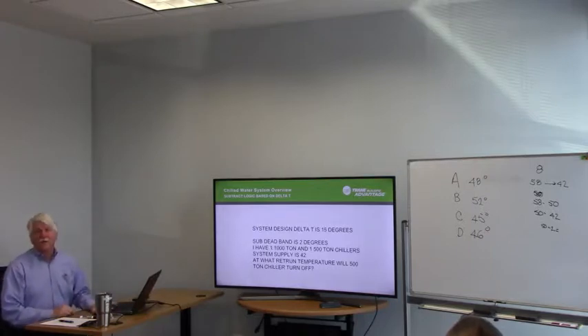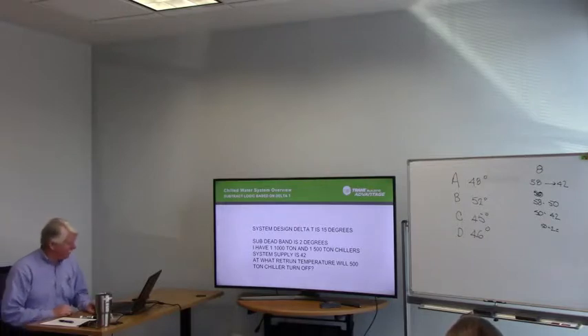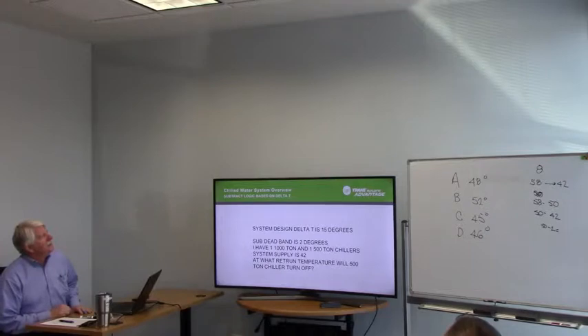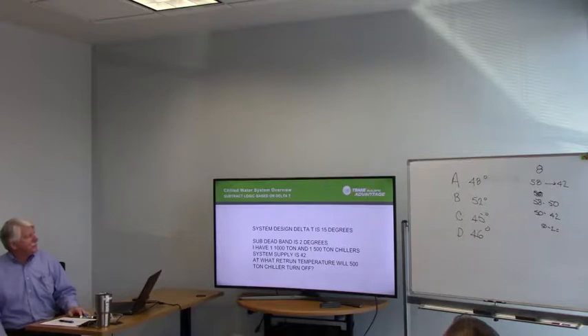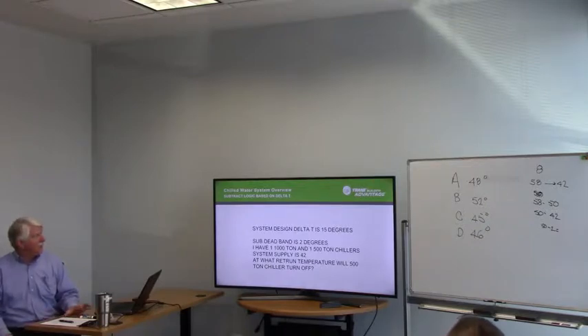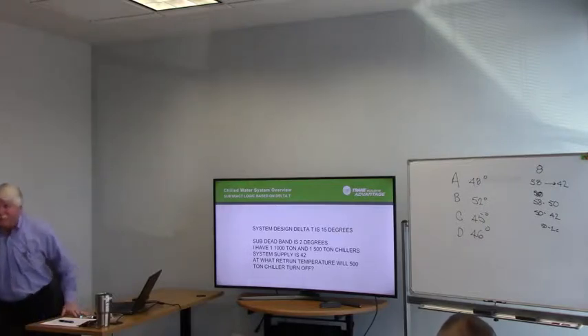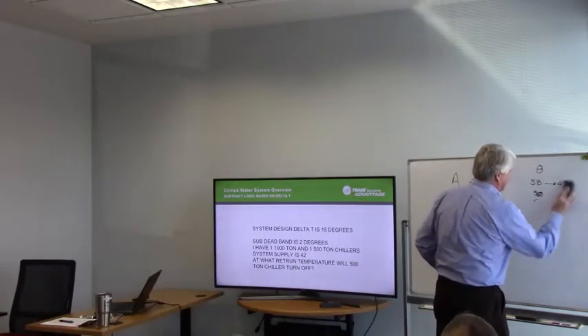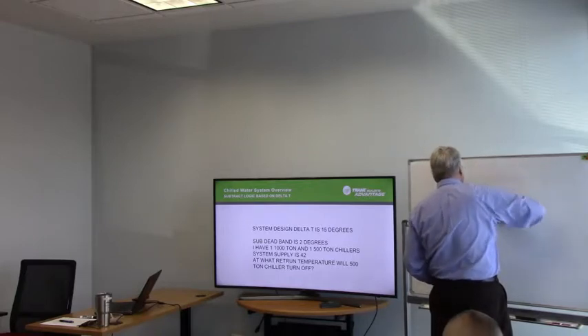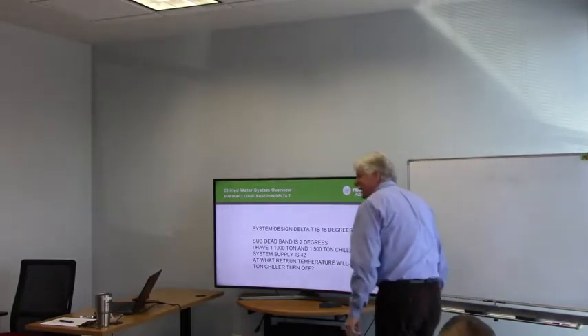Okay, now this is the hardest one you're gonna get, and it's the last question before lunch. I have a system delta T of 15 degrees. I have a subtract deadband of 2 degrees. I have a 1,000-ton chiller and a 500-ton chiller. At what return temperature will the 500-ton chiller shut off? I'm not gonna give you multiple choice.